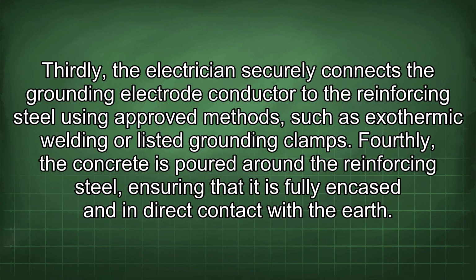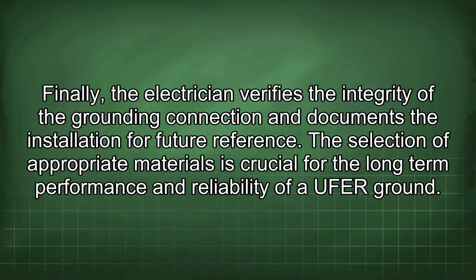Thirdly, the electrician securely connects the grounding electrode conductor to the reinforcing steel using approved methods such as exothermic welding or listed grounding clamps. Fourthly, the concrete is poured around the reinforcing steel, ensuring that it is fully encased and in direct contact with the earth. Finally, the electrician verifies the integrity of the grounding connection and documents the installation for future reference.